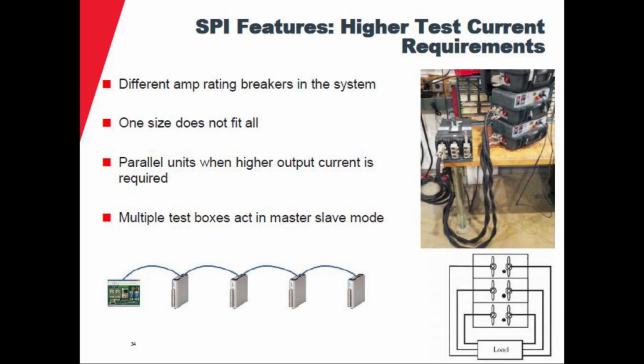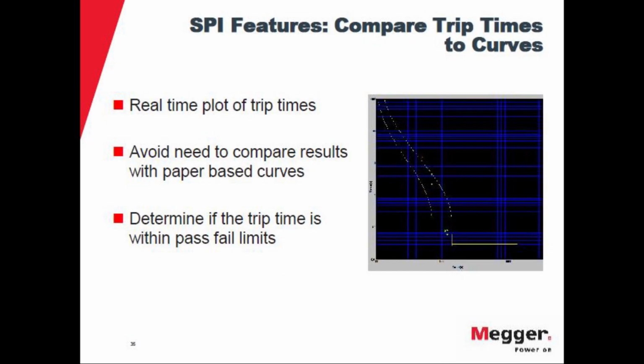They can be connected in parallel or series here at the output, so you can have higher current or higher voltage. And this is how the test results will show. So this is the actual screenshot of a curve from the circuit breaker, whatever was selected there. And these points that show here in green are the test points where the breaker tripped. Because they are inside this band, they look green, because that's a pass result. And here we have some red values that the breaker didn't pass, so it took too long to trip. The result is out of the expected time of operation.